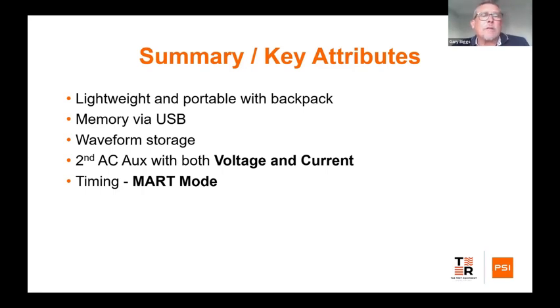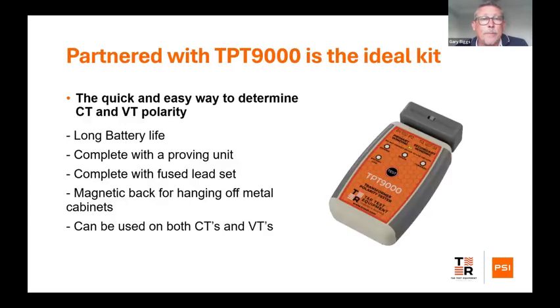As I said, we have that second auxiliary channel, which can give me both voltage and current, so I can test a much wider selection of relays. And we have the timing with the MART mode. You'll probably start seeing increasing numbers of relays across the world with that auto reclosing facility. Auto reclosing is to overcome issues where something's happened to a line, but it's not a permanent problem. It could be that a tree has grown and touched the line. The minute the tree touches the line, the energy will blow that branch away, so the problem's gone. But unfortunately, if you've got a relay that just operates, you've got to go out and find that fault. So that gives you a big advantage.